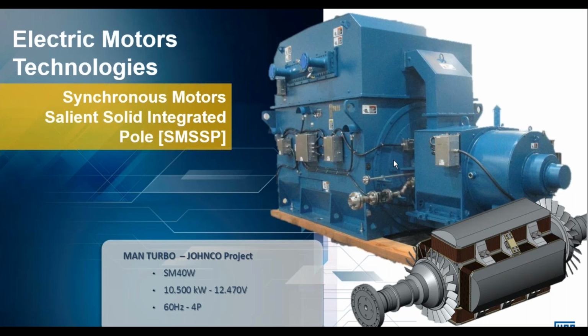looking at this design. This has some advantages in that you do not need a separate damper cage to start it. It is self-starting as it is. That is because enough induction is created on the pole shoe surfaces to overcome its own inertia and get this motor away. In addition, it has an advantage of having a very high starting torque. So for very high overload starting or high starting torque loads, this is a good synchronous motor option.